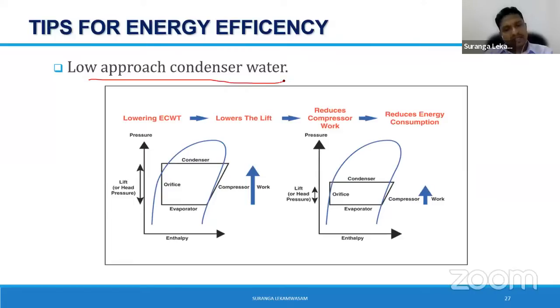Then, low approach condenser water. As we were saying, in old era buildings we had the condenser designed for 32 and 37, right? But now we design it for 30 and 35 with the support of good cooling towers, which is possible. When my condenser operates at 30 versus 32, you can understand my condenser saturation pressure reduces. Thereby my lift is reduced, which improves my chiller COP.